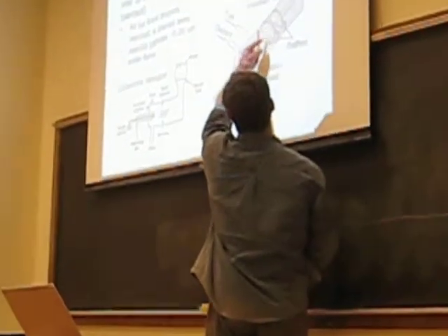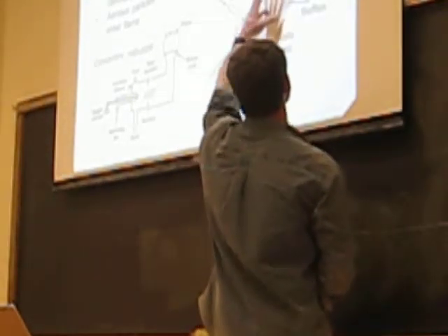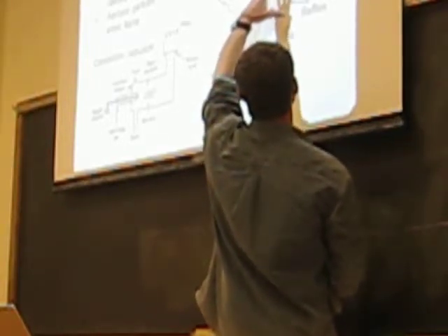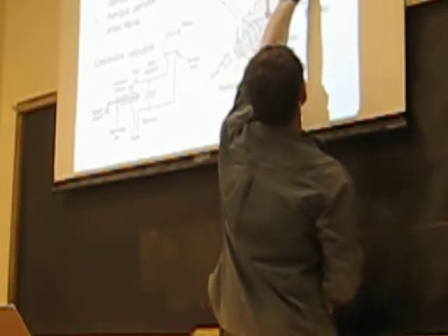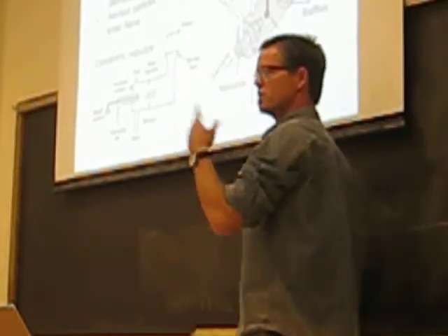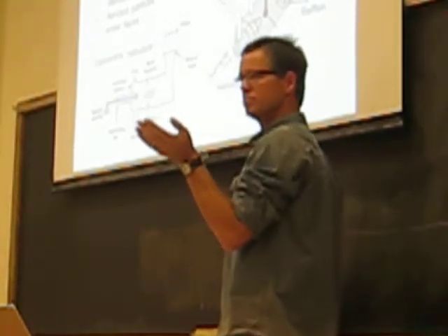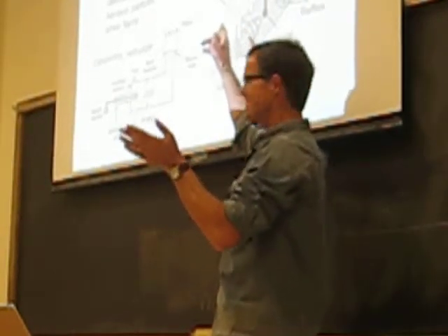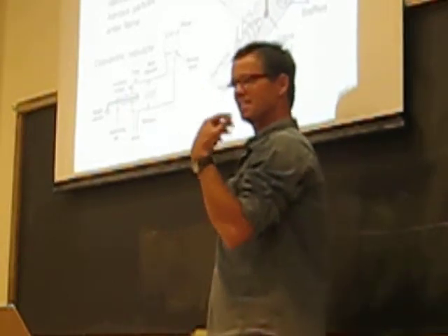And the mixture of the gases rushing through here, through these baffles that are shaped like a corkscrew, generate this Venturi effect of sucking the droplets that are in suspension, that are small enough to remain in suspension in the gas that's running through these baffles. And then they come up to the flame. And they have a mixture of this oxidant, which is what in your case? Air. Acetylene? Oh, air. Both. What's the oxidant? Okay, air, right? And the fuel is acetylene, right?